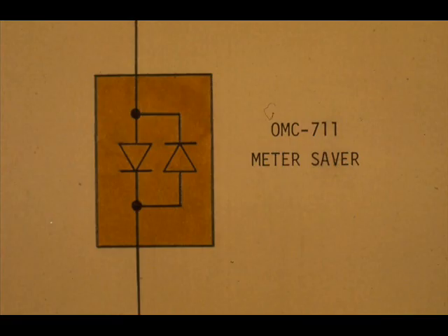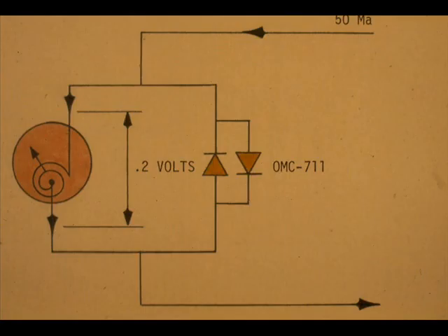The current would then flow through the OMC-711 device. The OMC-711 is called a meter saver. It is physically two back-to-back diodes. Two diodes are used to make the device goof-proof — you cannot hook it up backwards. When the meter is in parallel with the meter saver, there are only a few tenths of a volt across the diodes.